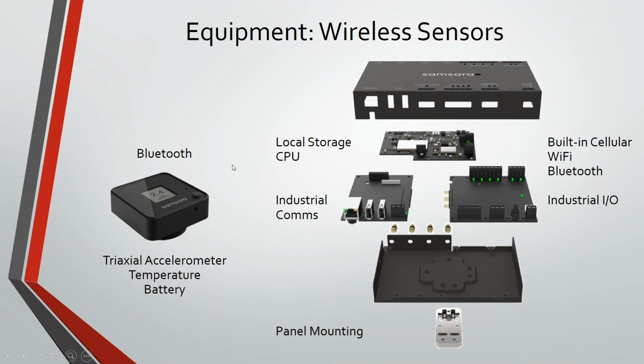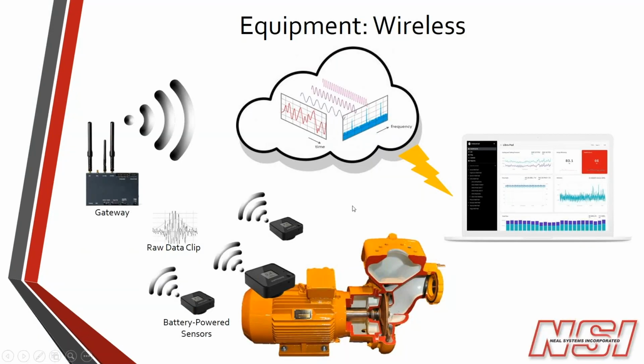And what it's doing is waking up every certain interval, taking a really small amount of data and then sending it to the gateway. And then the gateway is going to store it on local storage. And then most likely the gateway is going to use built-in cellular communications to put that data in the cloud. So you've got small chunks of vibration data coming into your gateway and going up into the cloud. Some of these gateways have industrial communications. Some of them even have industrial I/O. Most of them are going to belong in a panel somewhere. And so a typical setup is going to look something like this. A sensor is mounted on your assets, sending raw data clips to the gateway.